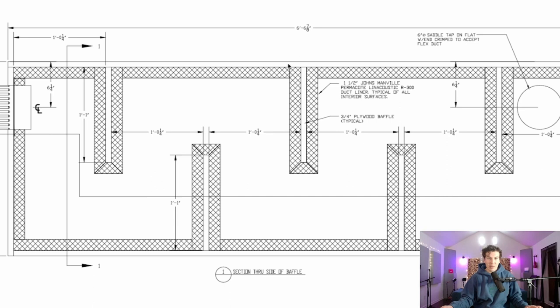The crosshatching in the design represents Johns Manville Permacote Linacoustic R-300 duct liner, typical of all interior surfaces. That stuff was pretty hard to find — I had to call around and special order it through a warehouse in Nashville that services special acoustic treatment for HVAC. It's a little expensive; I spent about $500 on all the insulation. I got five eight-by-four-foot panels, but four panels should be enough. The duct liner is one and a half inches thick.